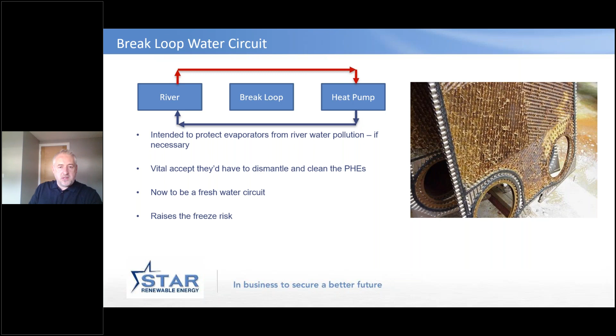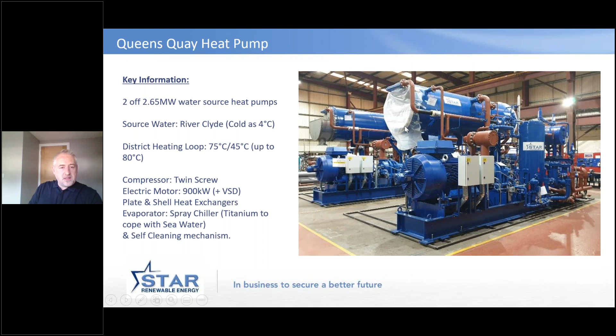So what we did was we built heat pumps with this tubular heat exchanger here. We call it a spray chiller. And in the bottom half, there's tubes that the river water passes through. They're made of titanium, so we're not worried about the corrosion of the tubes. And on the outside is the liquid ammonia that's being sprayed by the refrigeration system. We're also able to automatically clean the inside of the tubes. So why is 2 or 3 degrees worth having?